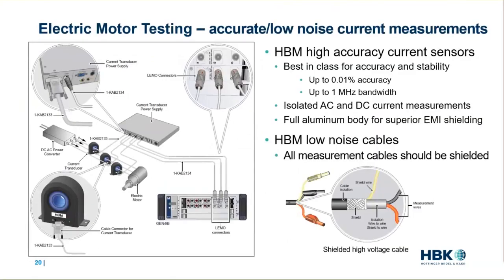Now, often the largest amount of error in many power applications, including electrical motor or generator testing, is in the measurement of current. Therefore, special attention has to be used to maximize accuracy and stability and minimize noise. So first, it's important to select a high accuracy and high bandwidth sensor. Often the sensor includes a power supply to power the sensor and the necessary low noise shielded cabling from the sensor to the power supply.